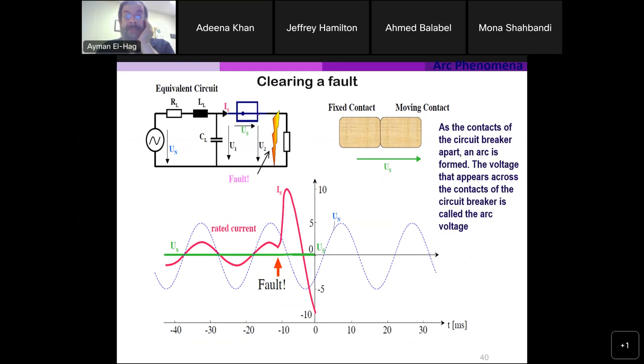You have a breaker that is normally closed, and this is the voltage across the breaker. It's a short circuit. Then a fault happened, and you want to open this breaker and clear the fault. The red line is basically your IS, the rated current. So we have a normal current here, and then at this moment a fault happened. When the fault happened, the current jumps to very, very high values. Now the breaker is closed, and it will start to open. It will take some time before it reacts to clear this fault current. And US is zero because it was closed.